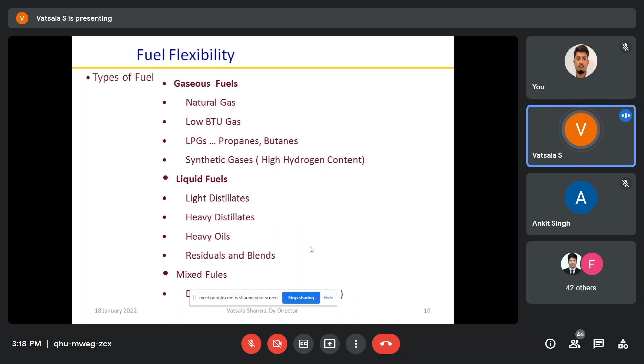To reduce the corrosive effect in the case of vanadium, magnesium is added in the ratio of 3 to 1, meaning 3 parts magnesium to 1 part vanadium in the fuel. At the time of combustion, vanadium pentoxide plus magnesium make magnesium orthovanadate. This compound raises the melting temperature of the ash above the firing temperature. So the melting temperature of the residual product after combustion is higher, and the chances of ash deposition and corrosion of the flue gas path are minimized.